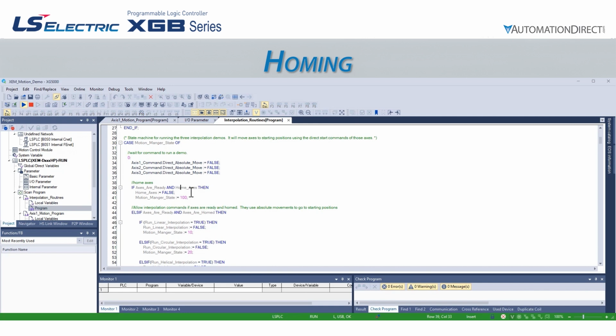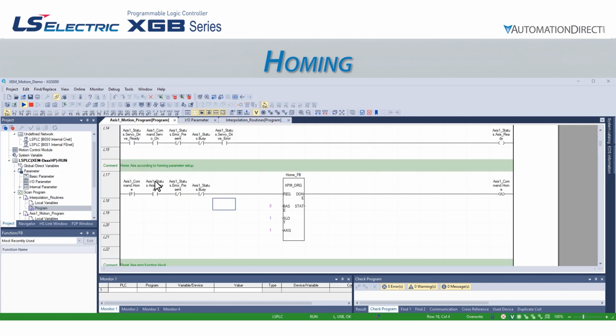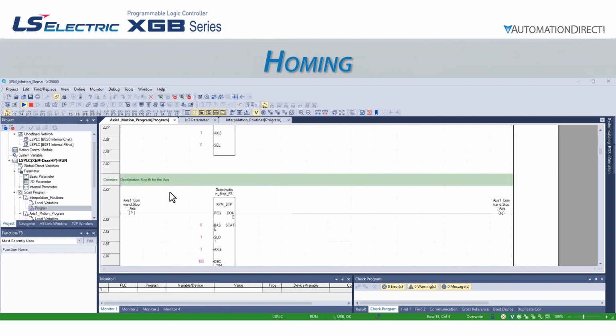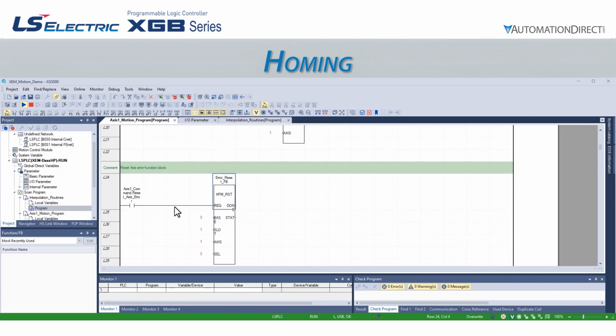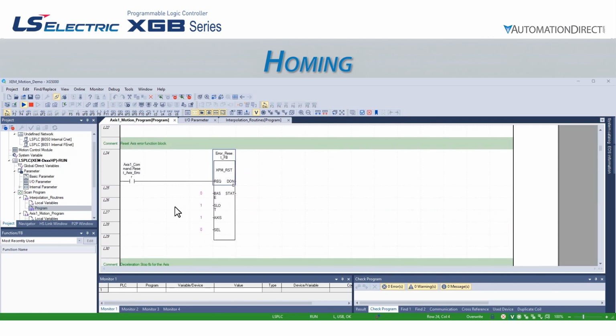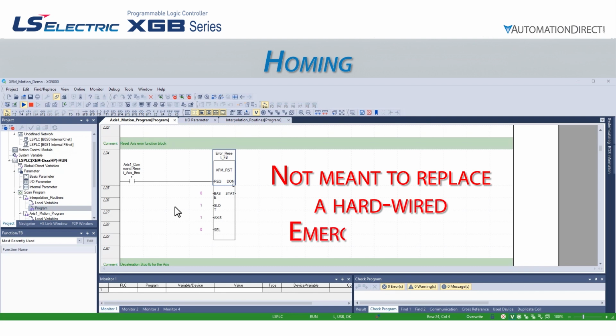Before we initiate any movement, it is important to note that we have functions in our project to stop motion using an XPM STP instruction, as well as reset any axis errors with an XPM RST instruction. We won't cover these functions here, but it is important to have them before executing any motion. Please also note that these instructions are not a replacement for a hardwired emergency stop. Please refer to your risk assessment to determine the safety needs for your application.